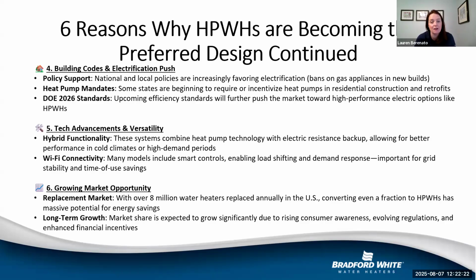It goes into effect on October 6th of 2026. What is so unique about this is that it's the first time in over 15 years that the DOE is really starting to regulate the efficiency of water heaters. And it's eliminating any product with a thermal efficiency below 95%. So where you see this is atmospheric venting. For example, gas water heaters will pretty much be entirely eliminated because atmospheric vents typically have a thermal efficiency of anywhere between 60 to 80.